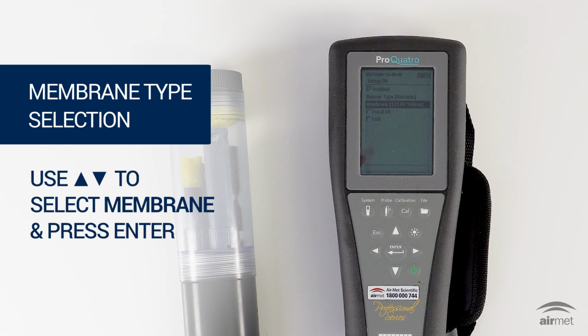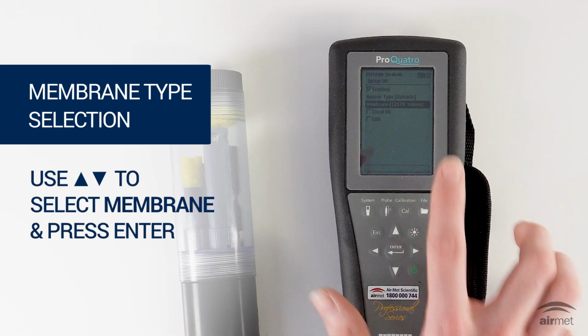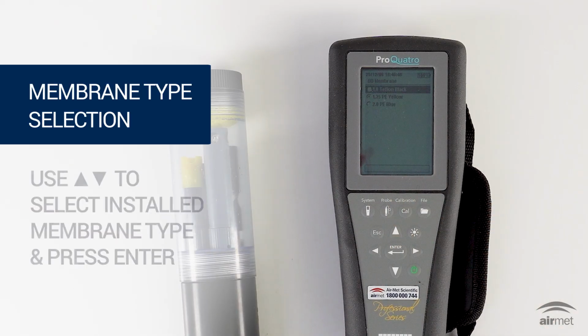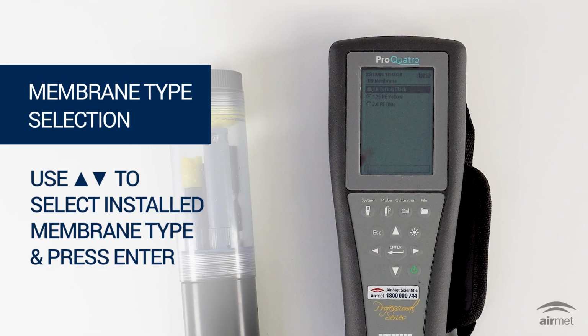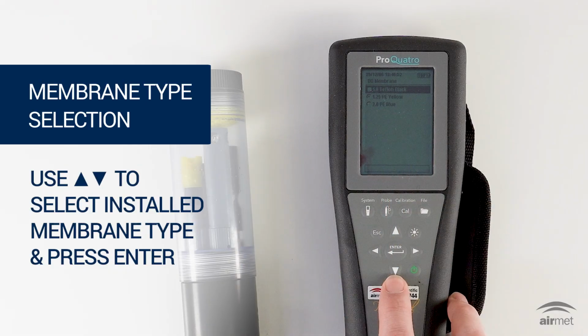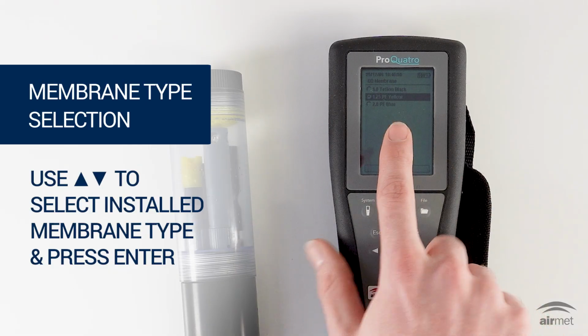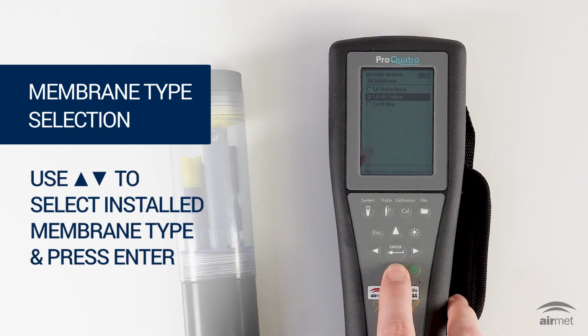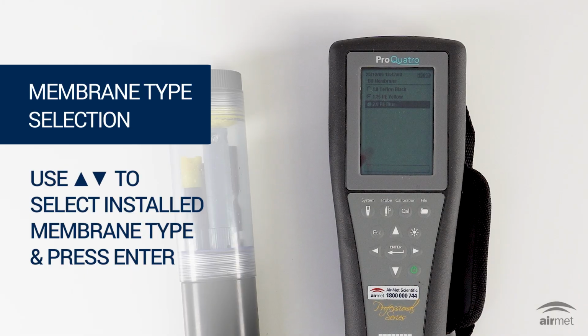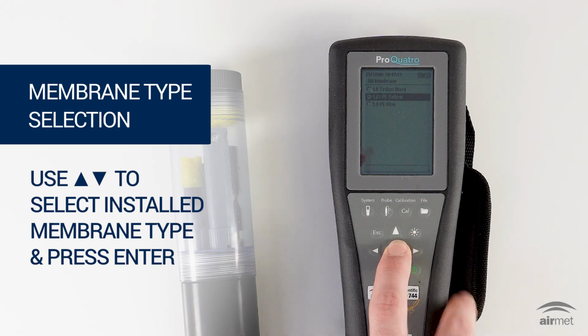Next, select the membrane type installed on the DO sensor. Highlight the membrane type and choose from 1 mil FEP Teflon, which is black, 1.25 mil polyethylene, which is yellow, or 2 mil PE, which is blue. The correct membrane thickness is essential for proper response time and DO diffusion characteristics. For our purposes, we'll select the 1.25 PE yellow membrane.